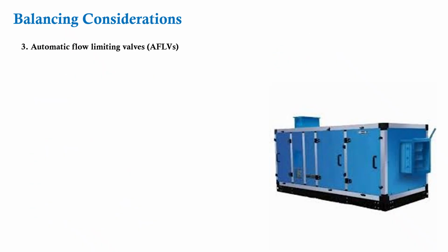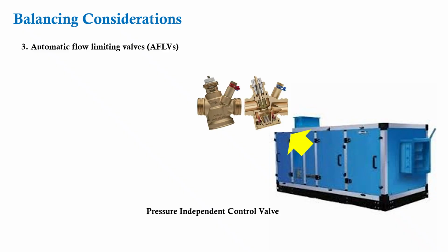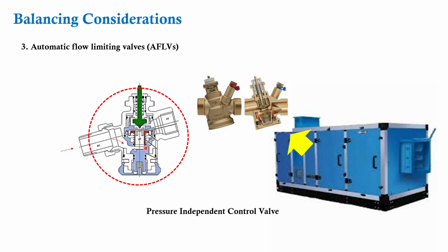I was talking about the pressure independent balancing control valves. Pressure independent balancing control valves eliminate the need for a manual balancing valve. It automatically balances the flow which is required to the AHU, and it also controls based on the demand. So where a mechanical or manual balancing valve is used, an additional one is not going to be required. I will make a separate video on the performance characteristics, how it really operates and adds value to the system.